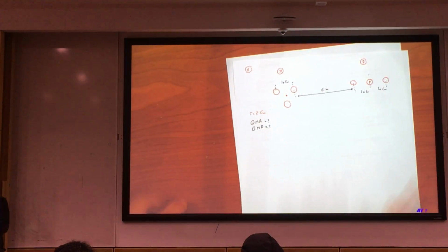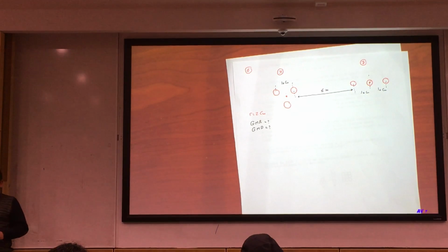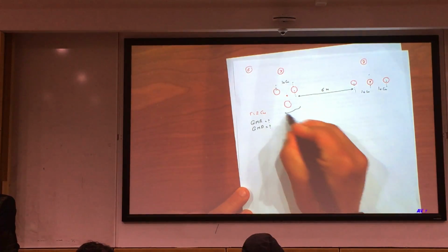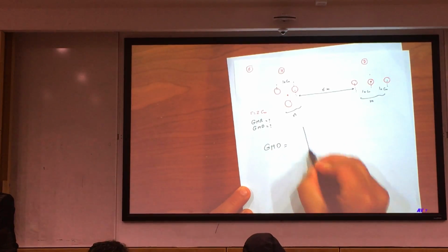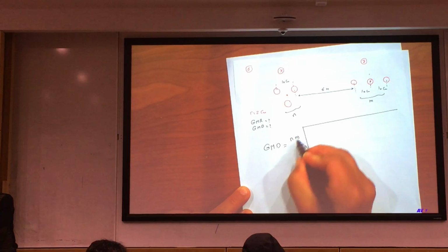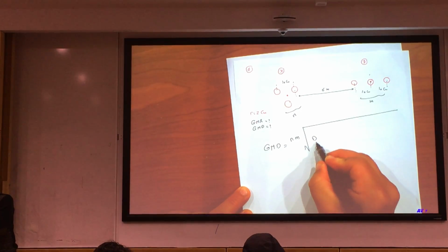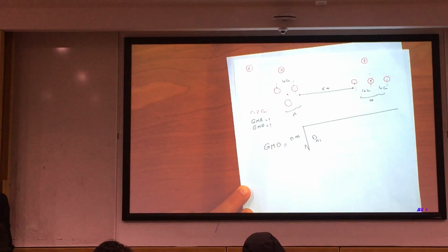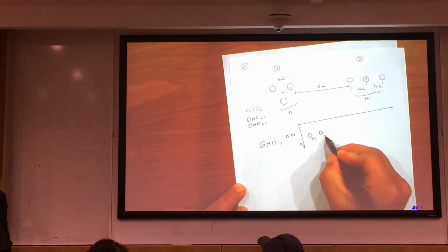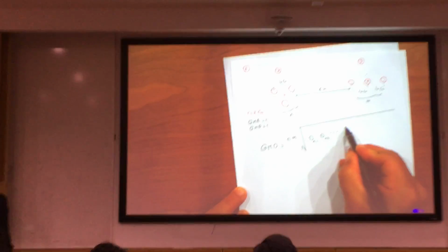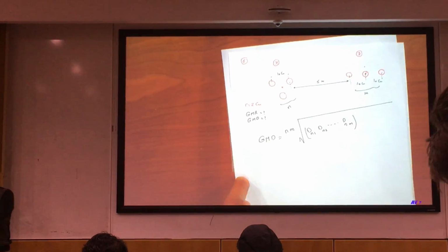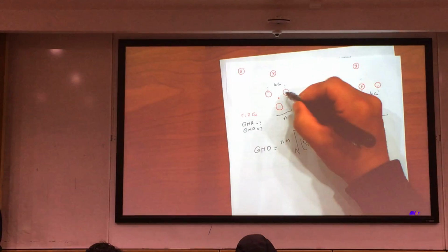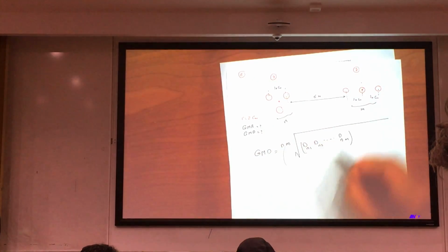But we have a general formula for such unsymmetrical arrangements, and I will explain this in the next lecture. That is, if I have n conductors here and m conductors here, the geometrical mean distance can be calculated from this formula. N times m, and the distance between D n1, conductor 1 in the m side, and D n2 in the m side, until the last conductor n and m. So what we have to do here again is to get these 3 conductors and apply this formula here.